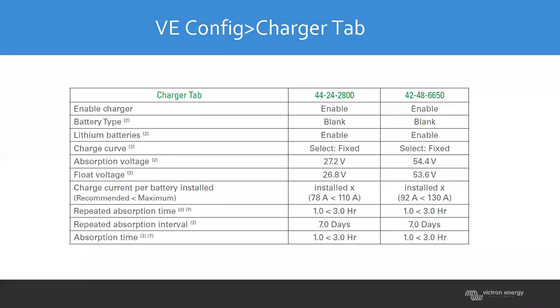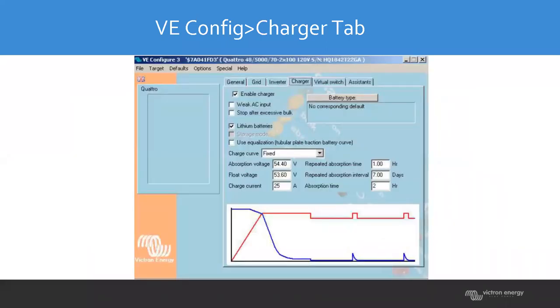So I'm going to get back to this. If you had just a grid for power on the inverter charger, you'd want to set that to maybe 260. But if you're off grid, we're going to have to look at that a little differently, and I'll get to that in just a moment. So repeated absorption time is going to be 1 to 3 hours. Repeated absorption interval is 7 days, and absorption time is 1 to 3 hours. So this is a screenshot of my charger tab.